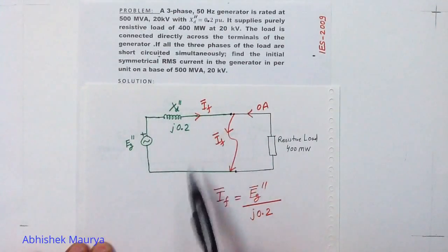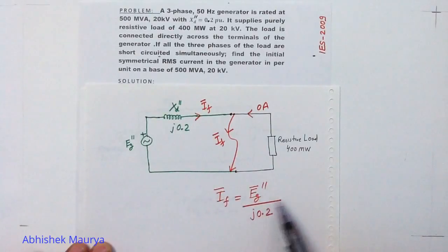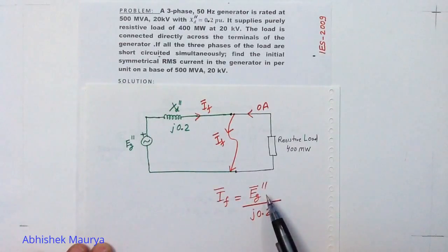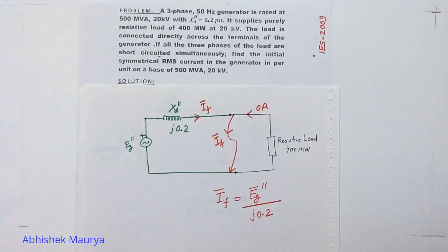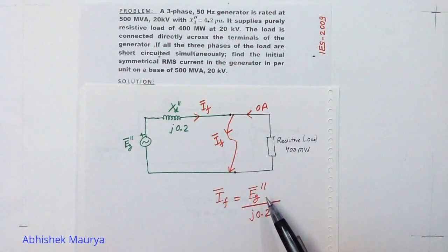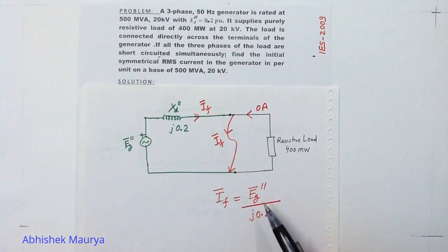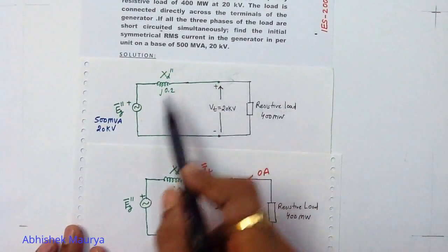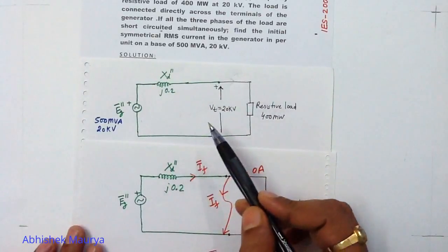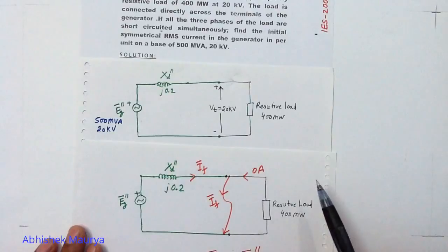After applying KVL you can write the equation: IF equals Eg double-dash upon J0.2. If you know the value of Eg double-dash — the sub-transient internal voltage of the generator — you can find the answer easily. This sub-transient internal voltage is always calculated from the pre-fault circuit, which is the circuit available to us just before the fault.